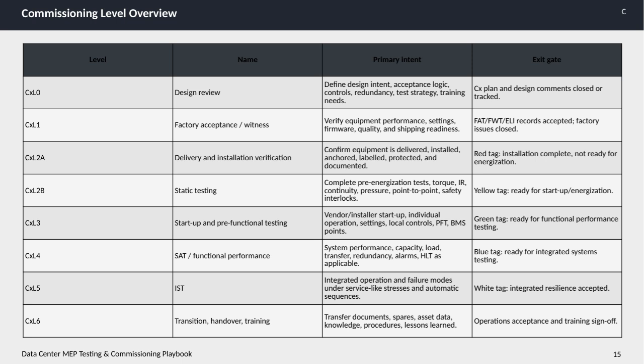CxL2 is split into two parts: delivery and installation verification, and static testing. The first confirms that equipment is delivered, installed properly, anchored, labeled, and protected. This stage results in a red tag, indicating installation is complete, but not yet ready for energization. Then, static testing involves pre-energization tests such as torque checks, insulation resistance, continuity, pressure tests, and safety interlocks. After successful completion, a yellow tag indicates readiness for startup. CxL3 focuses on startup and pre-functional testing, where the vendor or installer tests individual operation, settings, and local controls, as well as points connected to the building management system. Successful completion earns a green tag, signaling readiness for functional performance testing.